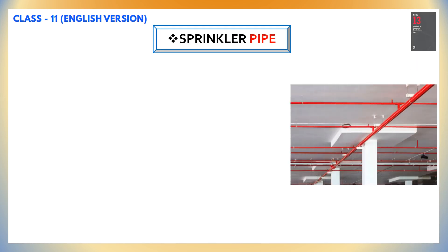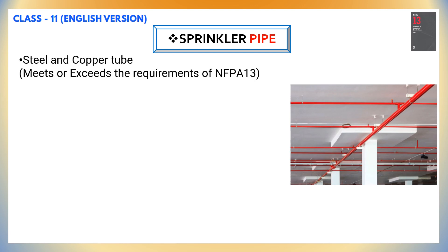Let's begin our class with the first system component: sprinkler piping used in the fire protection industry. As you can see on your screen, steel pipes and copper tubes can be used as sprinkler piping in line with the requirements of NFPA 13. Other piping materials can also be used; however, they have to be specifically listed for fire protection service.